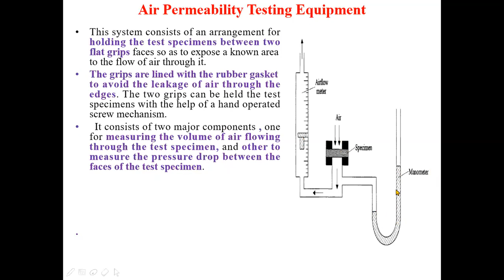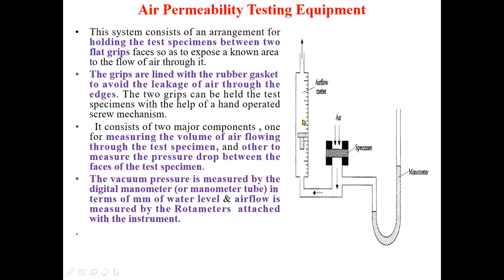The vacuum pressure is measured by the digital manometer or the manometer tube in terms of millimeter of water level, as I've already told you. This is the 10 millimeter, and the airflow is measured by the rotameter attached with the instrument. This is the rotameter, or floats, you can say. These floats will move up and down depending upon the flow of air. Okay, if the flow of air is very high, then the height achieved by these floats will be higher.